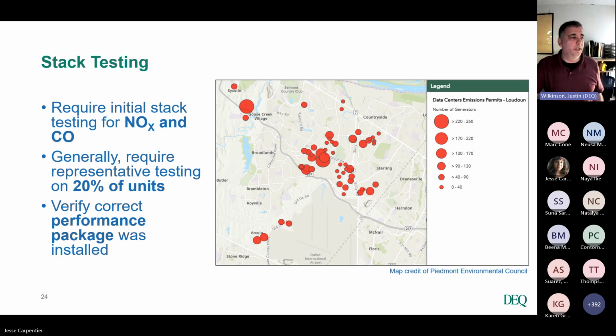So concurrent with the CO and the NOx, we'll do visible emissions evaluations to demonstrate compliance with the opacity limitations that we put in the permit. Our opacity limitation for emergency generators in Northern Virginia is very low. It's 5%. So really seeing any visible emissions coming out of the stack would indicate to us that the unit's not set up properly. There might be a problem or an issue. So really those tests are verifying that the unit is set up appropriately.